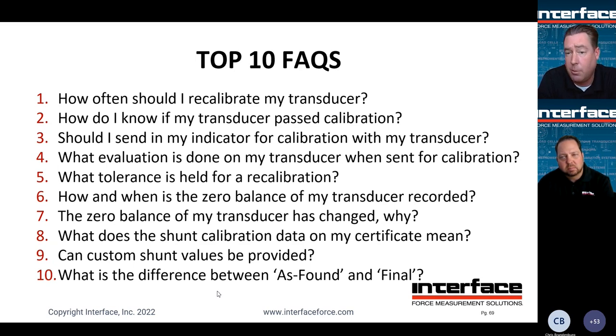Are we seeing an insulation resistance breakdown on the load cell that could be a sign of either a wiring issue or other damage inside the load cell? And of course, what is the zero balance of the transducer? We want to make sure that the sensor is in a good enough condition that, for instance, if it has a bad IR condition and we put it on one of our calibration rigs, that causes other problems for our instrumentation. So we want to make sure it's suitable for that and make sure it is in good shape for the cal.